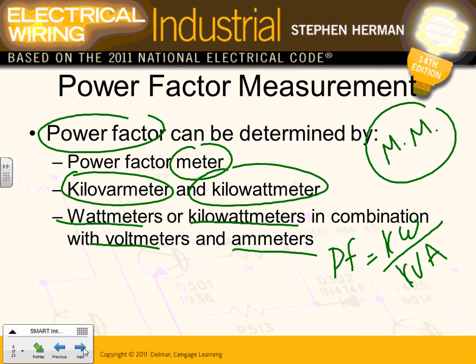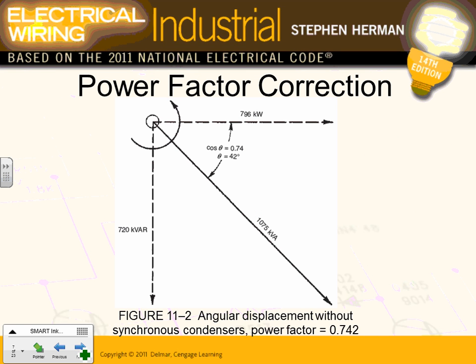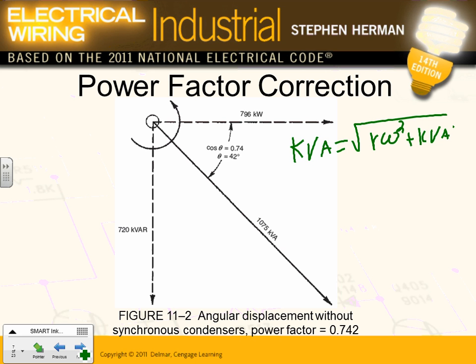What quantities do you need? These are the quantities that you need to calculate them. This is one of the single most important tables that you guys are going to see. We will work on this one tomorrow in the calculation, but I want to remind you guys that kVA equals the square root of kW squared plus kvar squared. So this is my kVA, and this is my kvar, and this is my kW. That's the so-called power factor correction power triangle. This is your power triangle.